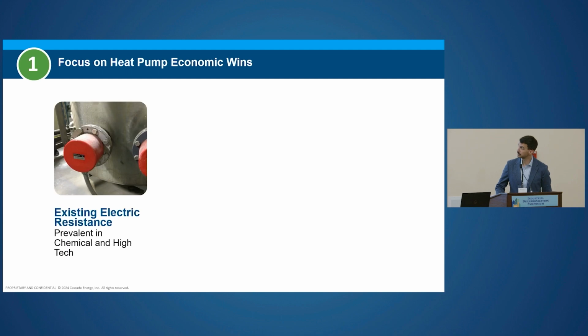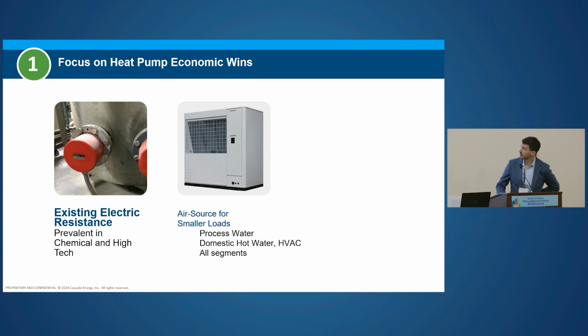So this was broken down into a few categories. So one of these was the situation where you've got electric resistance in the baseline. So this was at a chemical site, just a tank of hot water, 180 degrees F, and just heating it with electric resistance heat. So this provides a great opportunity just for converting to heat pumps right away. And this was fairly prevalent in these 2 segments.